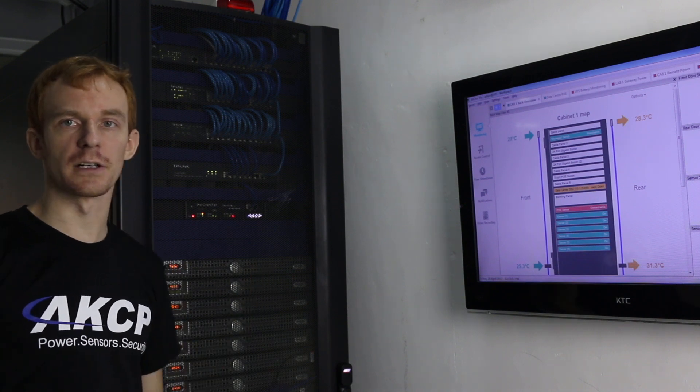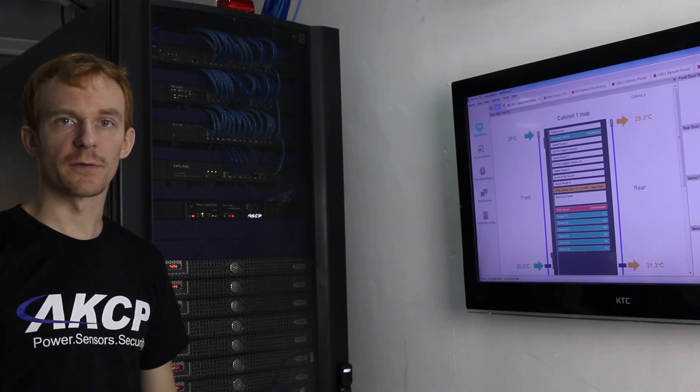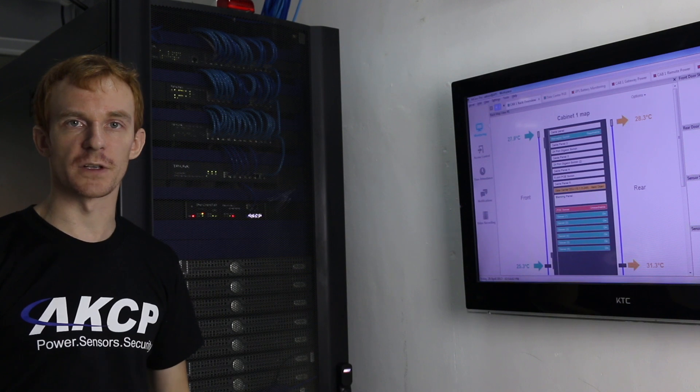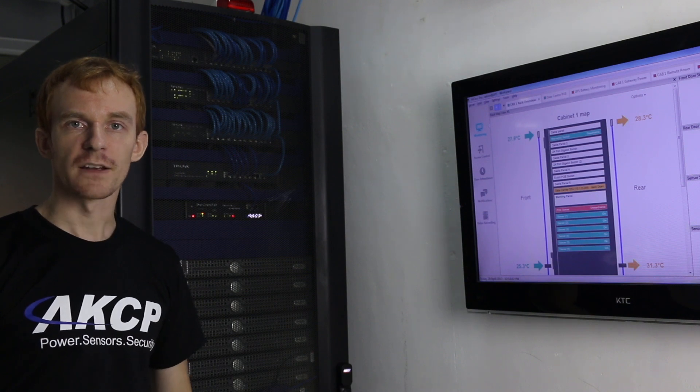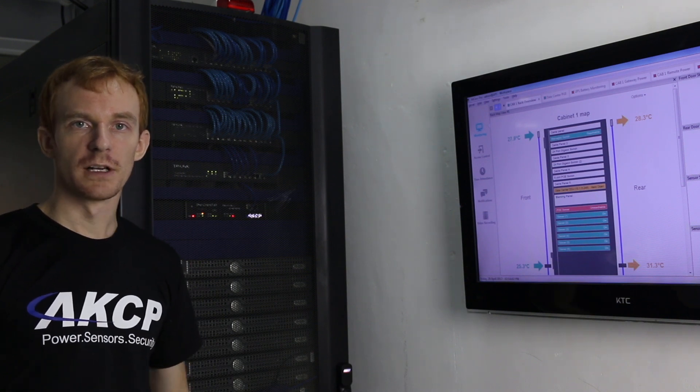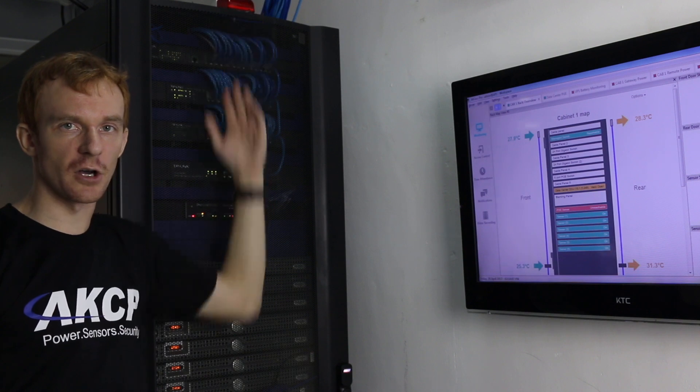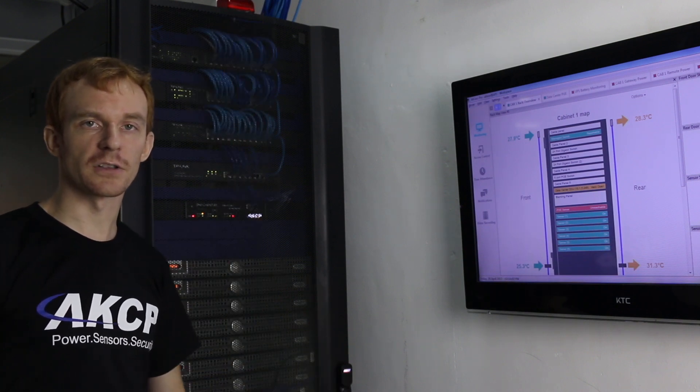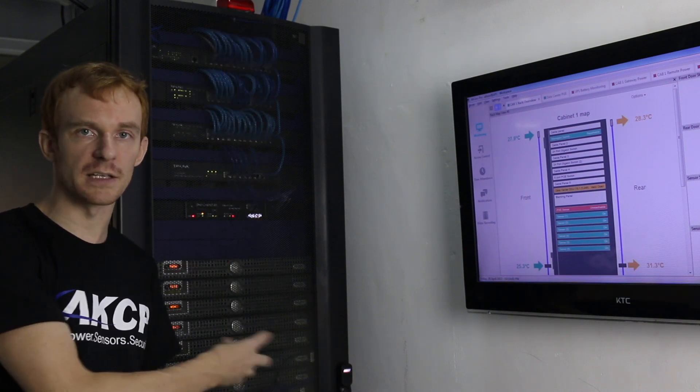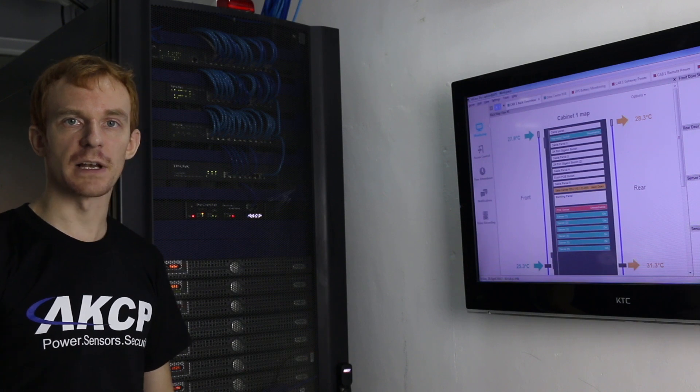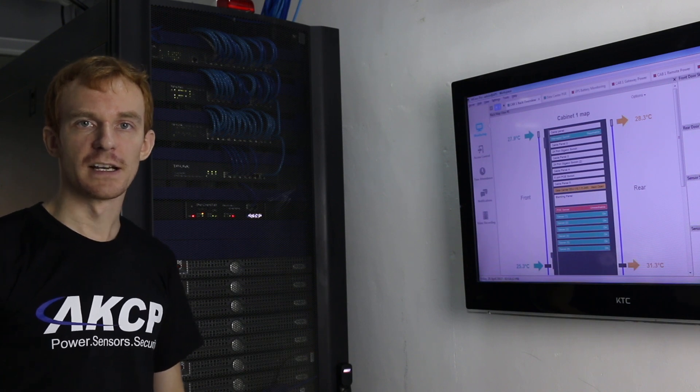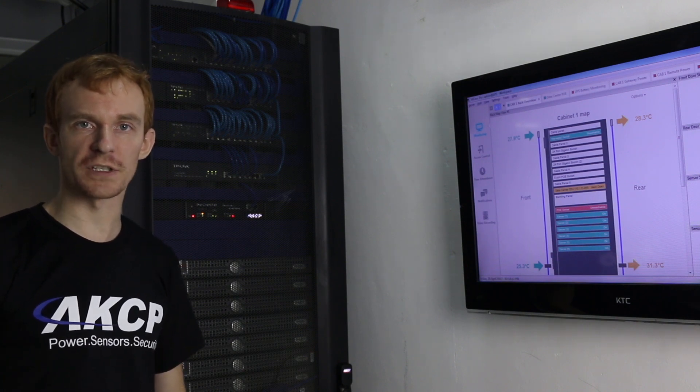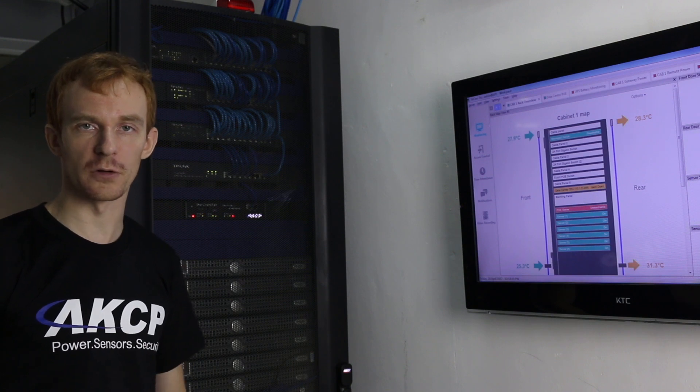Installed on our test cabinet behind me, I've got thermal map sensors at the front and rear. The thermal map sensor tells us the temperature at the top, middle, and bottom of our cabinet, measuring the cold air being drawn in at the front as well as the humidity. That makes it a four-in-one sensor—four sensor points on a single port.